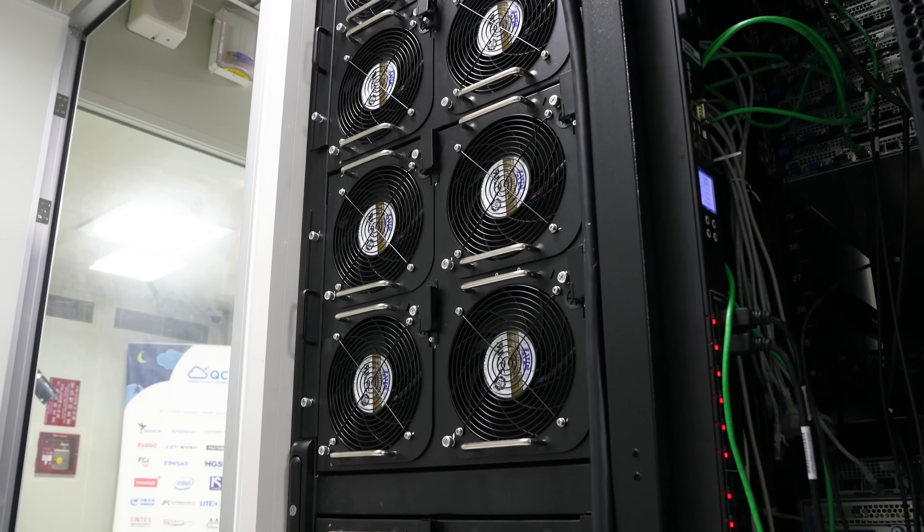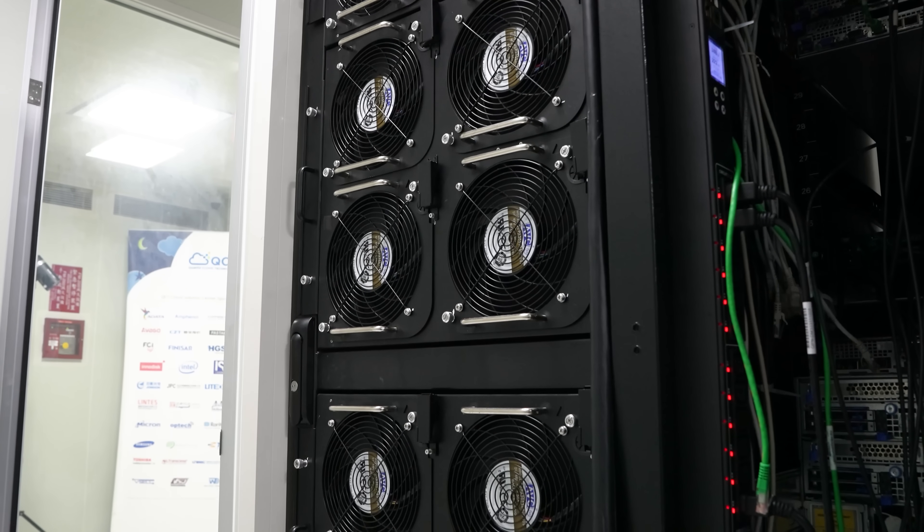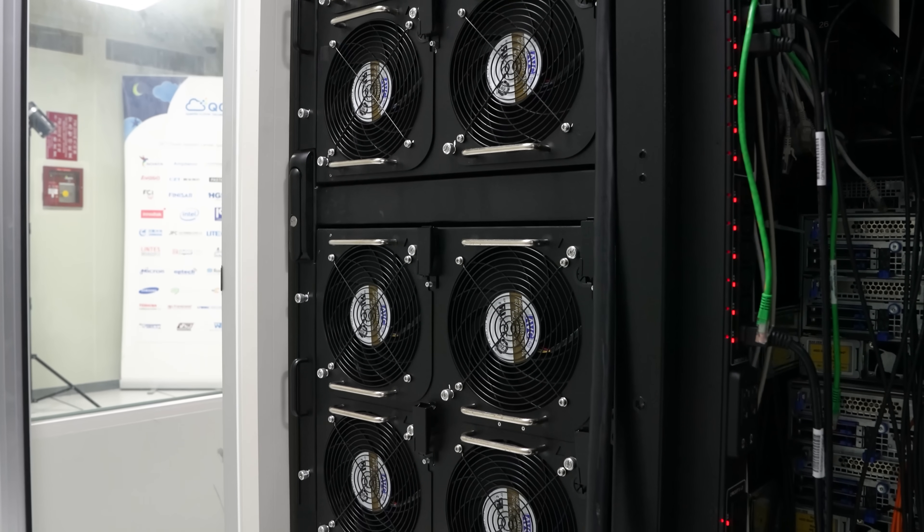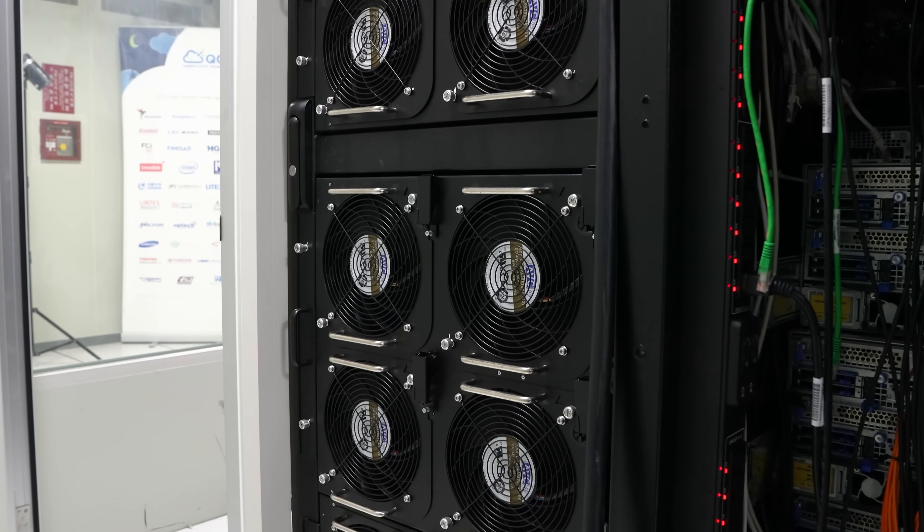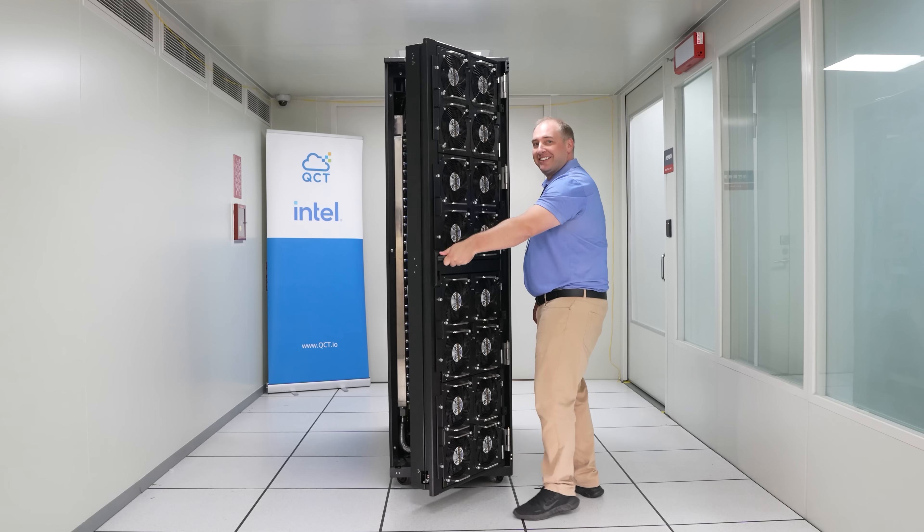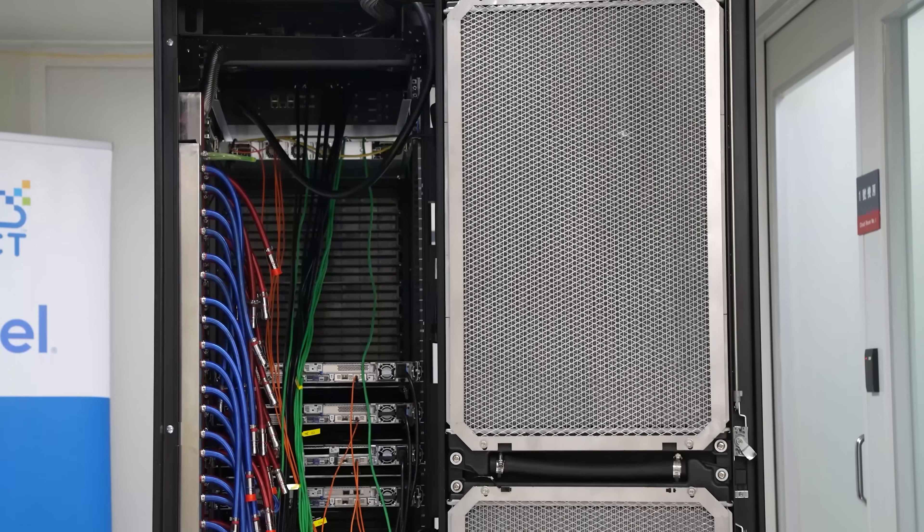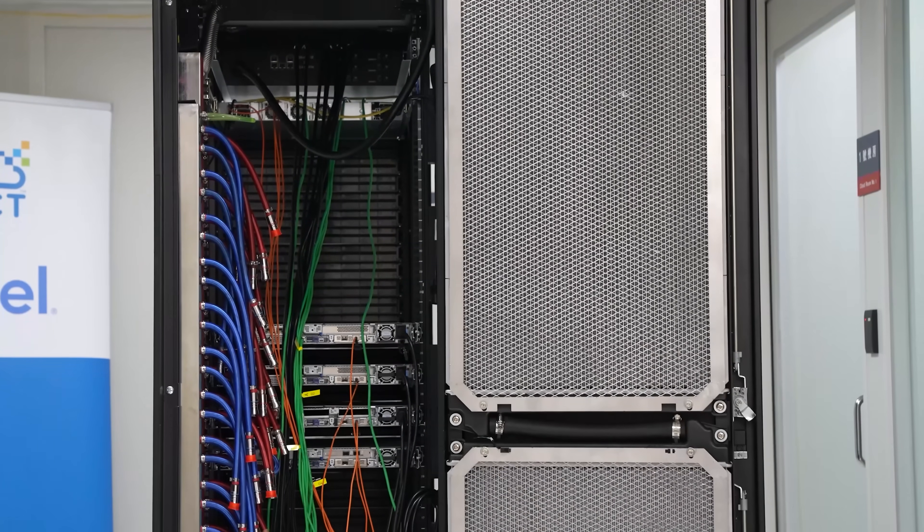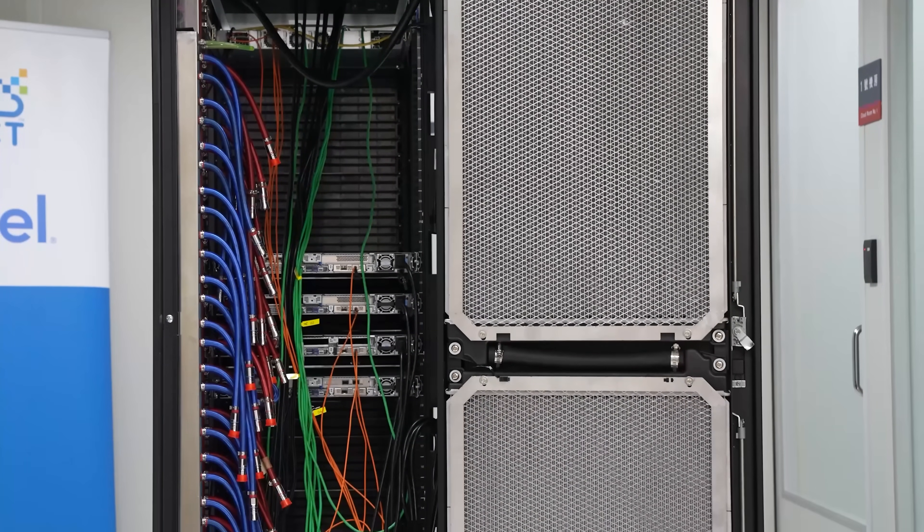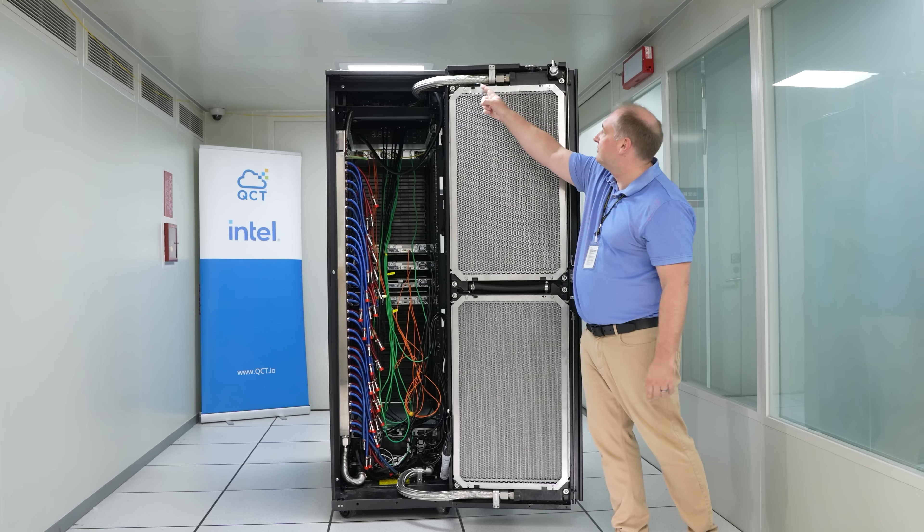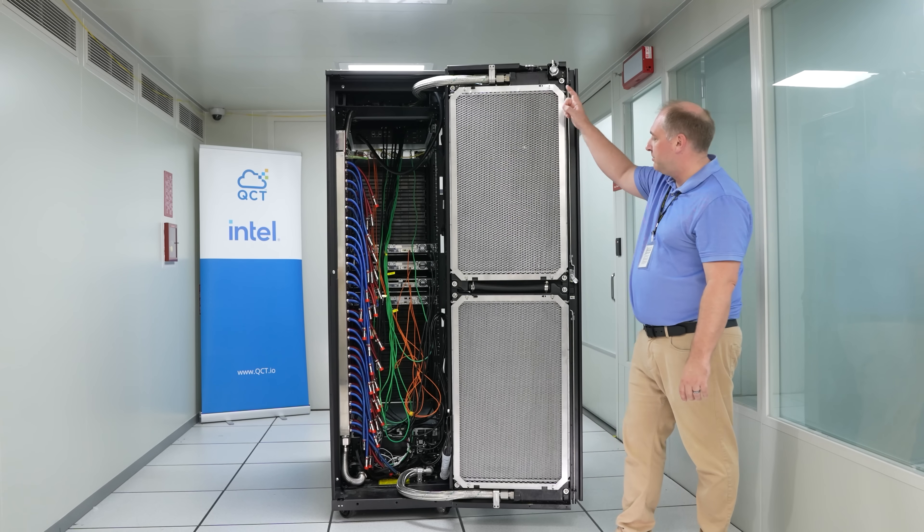Because when you go to the back of the rack, you're going to see something totally different than most racks that you'll see, and that is a giant wall of fans. Now, these giant fans move a lot of air relatively efficiently, and you might be wondering, what are those fans for? And when we open up the door, you can see exactly what's in there, and that is these giant radiators. And let me just point out real quick that this is super useful for folks, because if you don't have enough cooling just in your data center to go and deal with the heat generated from all these servers, and you also have enough power, well, this is a liquid cooling option that doesn't require things like facility water.